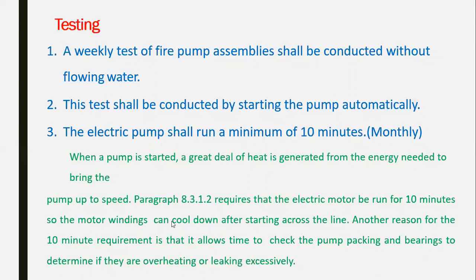When the pump is started, a great deal of heat is generated from the energy needed to bring the pump up to speed. Section 8.3.1.2 requires that the electrical motor be run for 10 minutes, so the motor winding can cool down after starting across the line. Another reason for the operation for 10 minutes is to allow the time to check the pump packing and the bearing to determine if there is overheating or leaking excessively. So running for 10 minutes, this is for the electrical pump.